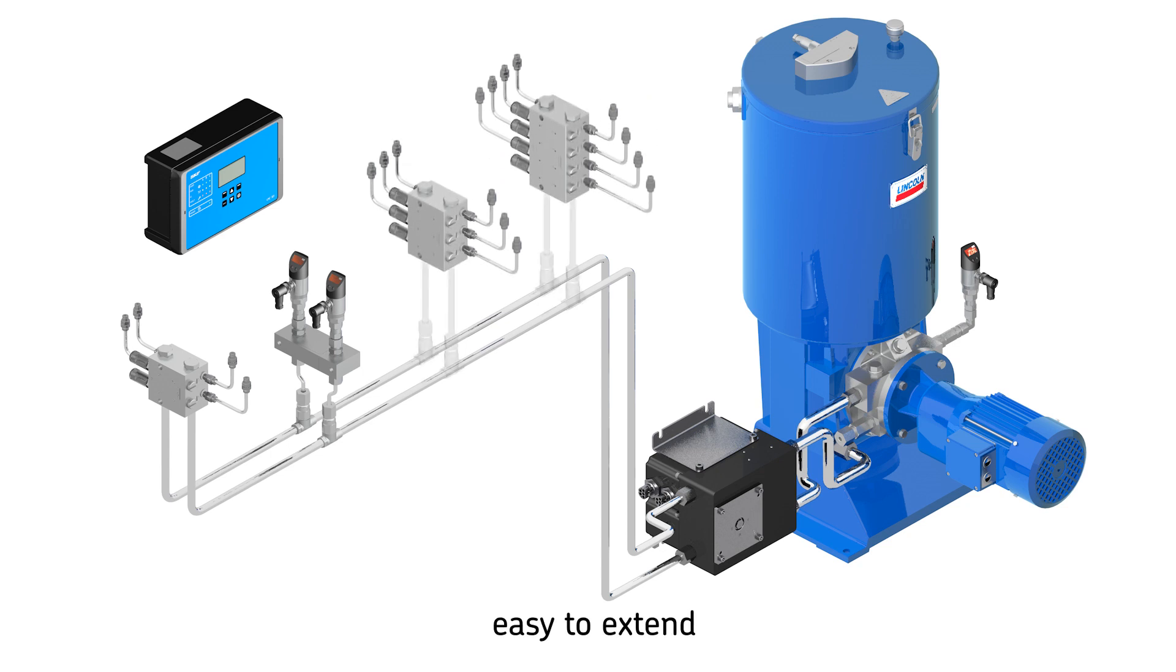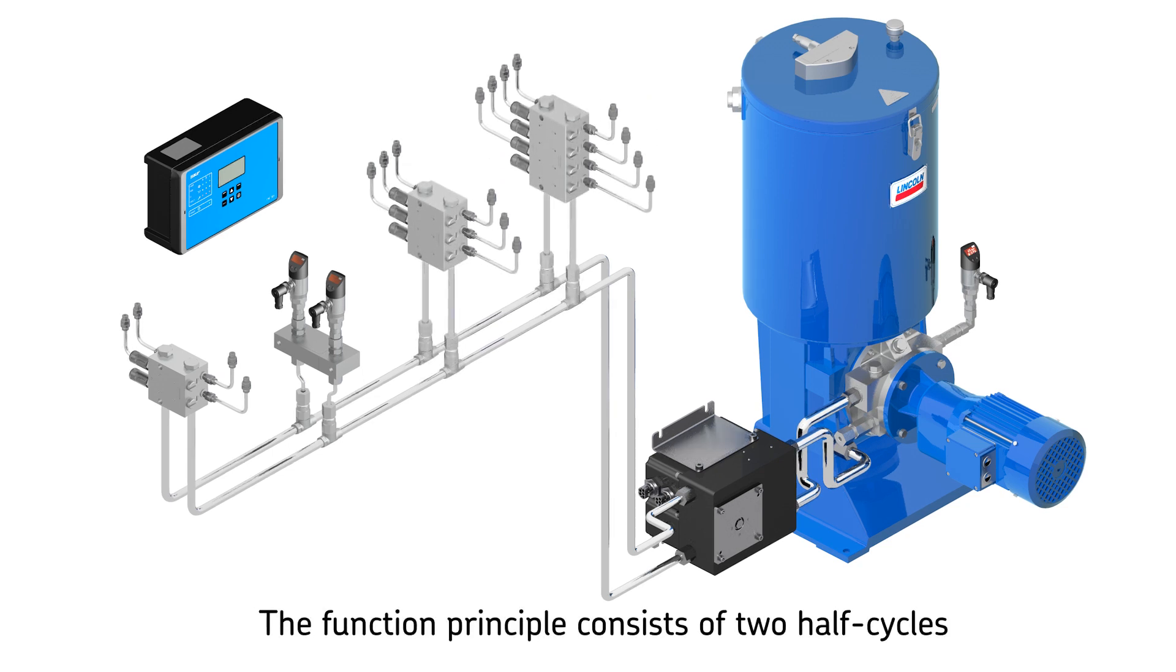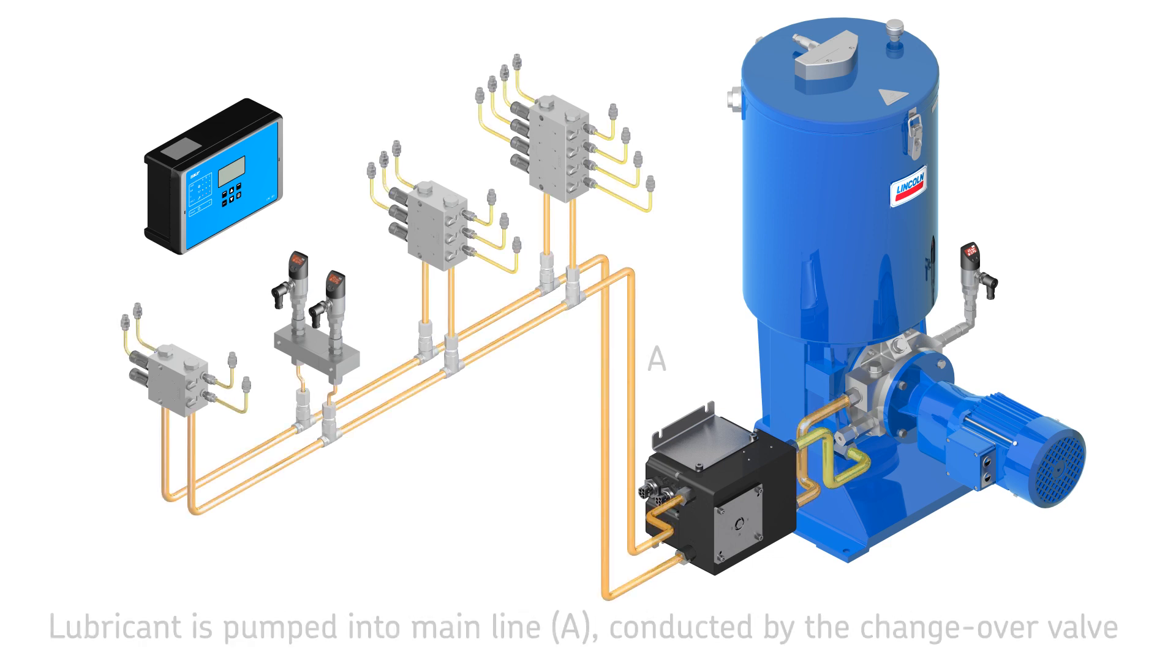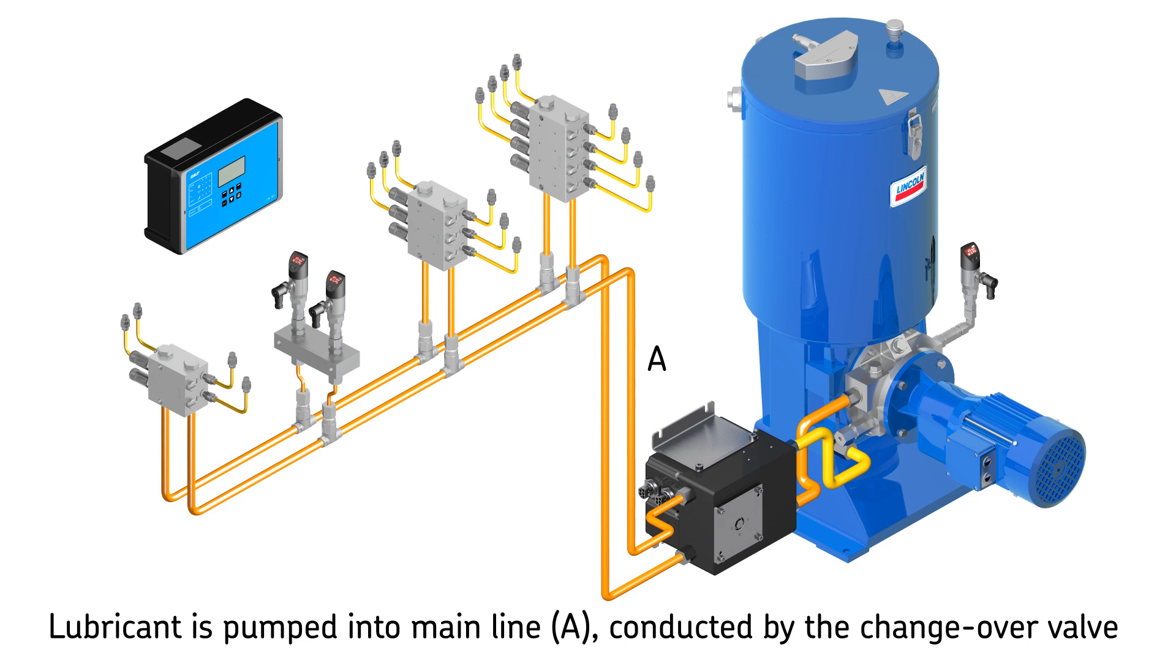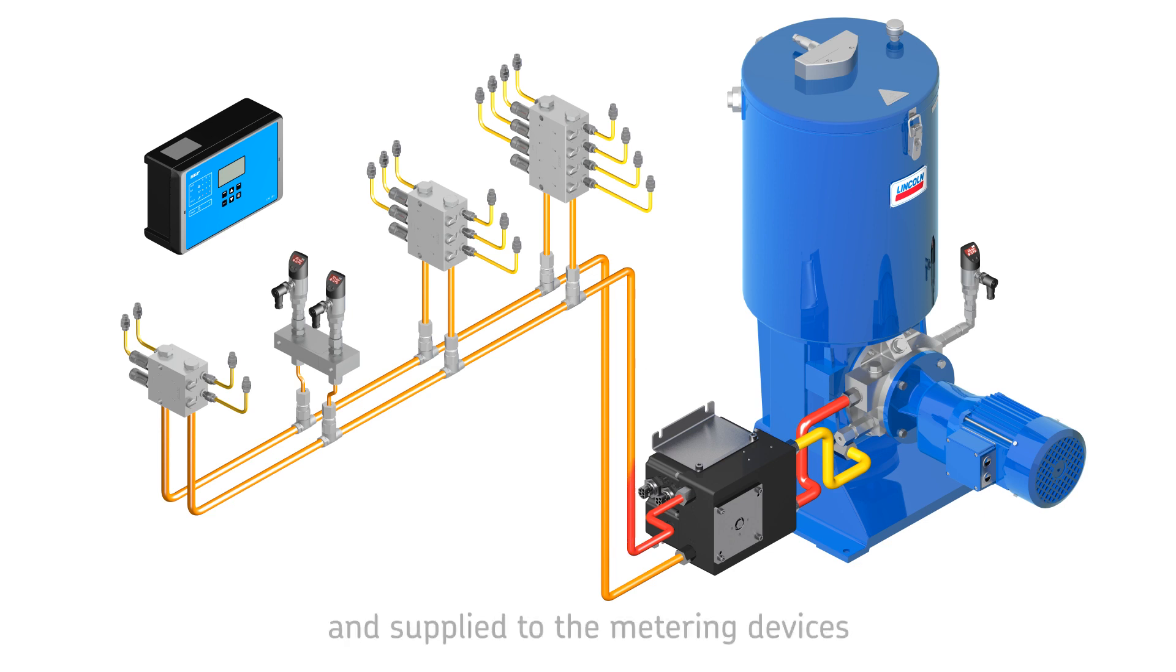The function principle of the dual-line system consists of two half-cycles. In the first half-cycle, the lubricant is pumped into main line A. The second main line B is connected to the relief line.